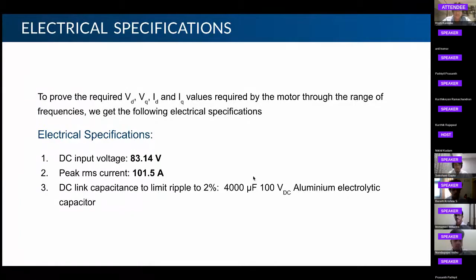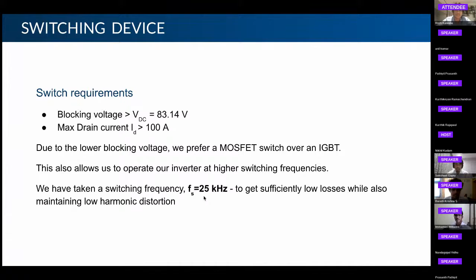As the blocking voltage is relatively lower, we would prefer to use a MOSFET switch rather than an IGBT because it has lower losses and can operate at higher switching frequencies. We have also taken a switching frequency of 25 kilohertz because this provides low enough harmonic distortion, and if we go for higher switching frequencies, there may be an increase in temperature and also higher losses.